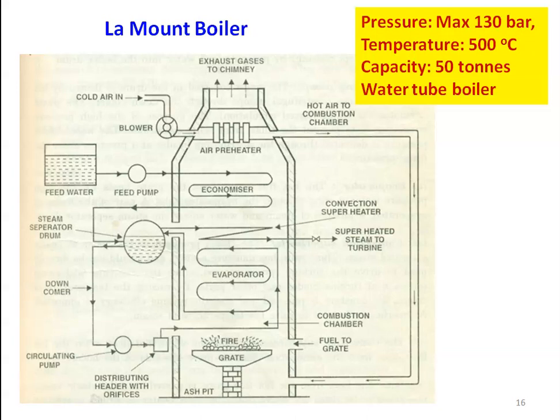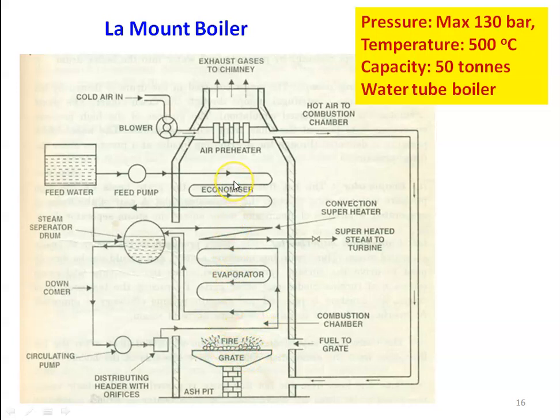The various parts of the Lamont boiler, starting from the bottom: we have a vertical boiler shell, and we have the grate. Below the grate we have the ash pit. In the grate, the burning of the fuel takes place. Through the small opening on the right-hand side, we supply fuel to the grate and hot gases are produced. These hot gases flow in the upward direction, first heating the evaporator, then the superheater, economizer, air preheater, and then leaving to the atmosphere. All these components are shown by lines indicating tube bundles — a number of horizontal tubes are arranged so that hot gases flow between the tubes to heat the water, heat the steam, and heat the incoming air.